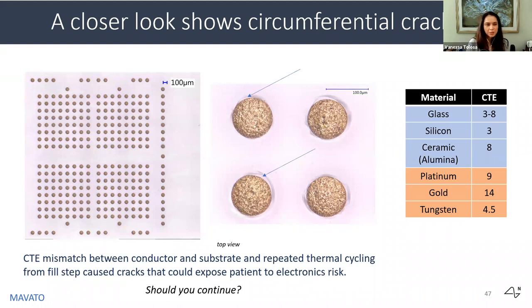And if you look at this table on the right, this is why for medical device implants, the conventional materials for feed-through substrates are ceramic and platinum. Look at how well they're matched, it's like 8 and 9. Unfortunately, due to some of the issues I've discussed earlier around via holes and mechanical robustness, this particular combination of materials is currently limited to larger sizes and lower densities than what we need.